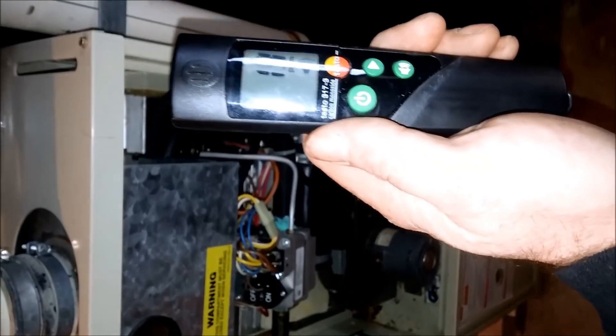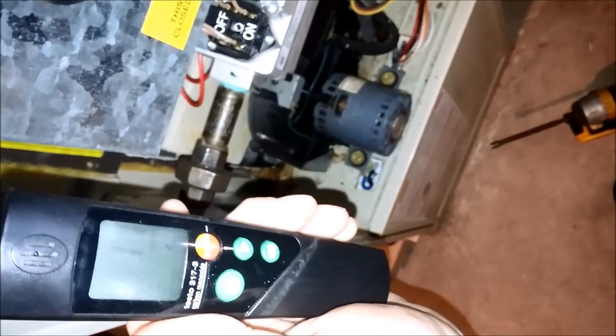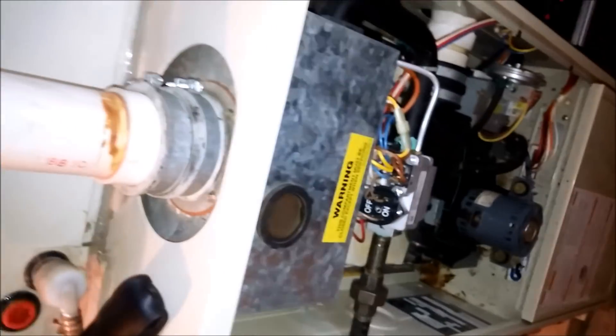Let me air this out and see if we've got any CO in the house. Inside by the furnace I'm getting 15 to 17 parts per million, so this furnace is done. This is a 398 AEW Bryant from 1989, and we'll do a heat exchanger inspection.